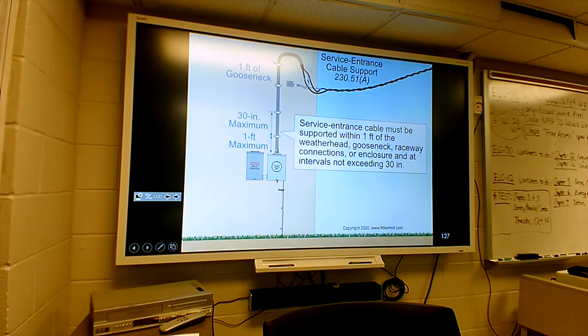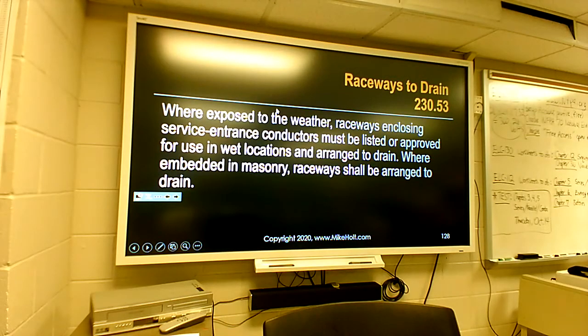Cable supports for service entrance cable. Here they're showing it must be supported within 1 foot of your weatherhead, gooseneck, or raceway connections at the enclosure, and the interval is not exceeding 30 inches. So you gotta have it supported within the first foot. After that, every 30 inches maximum. And where exposed to weather, your raceways enclosing your service conductors must be listed or approved for use in wet locations and arranged to drain. Where they're embedded in masonry, they shall be arranged to be able to drain.